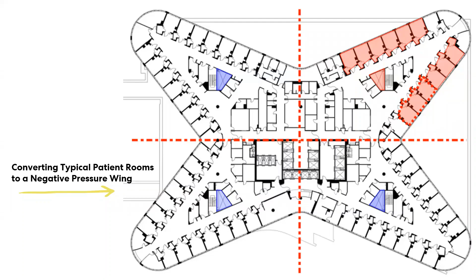So as we looked at in the other plan, there are a couple of isolation rooms per floor, but in a surge mode, we need to be able to accommodate more patients, we need to isolate a higher level of patients. So when we look at the floor plan, the patient tower is separated from a mechanical standpoint into 4 quadrants. Each of the risers serving those quadrants is highlighted in the diagram that we're looking at now. The 4 blue outlined shafts are dedicated to each of the quadrants they're located in. And if we look at the right-hand corner, the red riser serves the red patient rooms along the perimeter. So let's zoom in on the area there that's in dashed in the next slide.